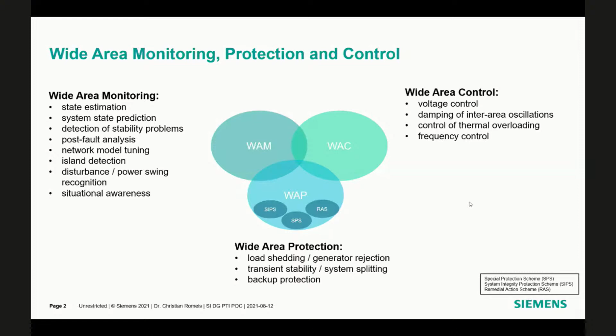Our idea is that in the future you can adapt these schemes using information from wide area monitoring or wide area measurement systems, adapting them to the actual system state — for example, changing load shedding actions, generator rejection, or the action taken in case of a transient stability problem, such as splitting the system at a different point in the network. Wide area protection can also serve as backup protection.